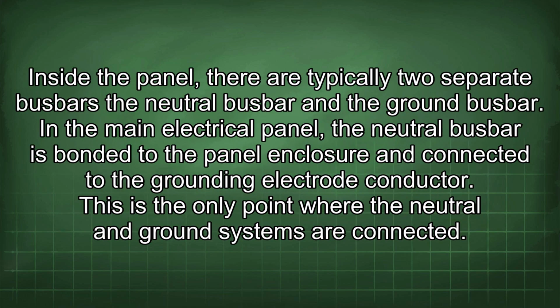Inside the panel, there are typically two separate busbars, the neutral busbar and the ground busbar. In the main electrical panel, the neutral busbar is bonded to the panel enclosure and connected to the grounding electrode conductor.